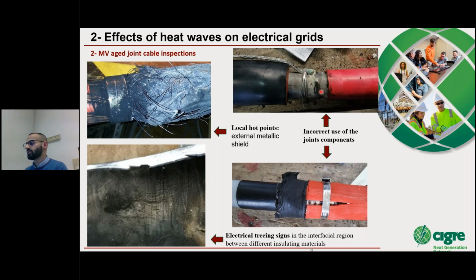In this case, there was incorrect use of all the components provided by the manufacturer. Here, a wire made possibly of iron was used, and only one component was used instead of two to ensure the contact between the metallic shield of the joint and the external metallic shield of the cable.